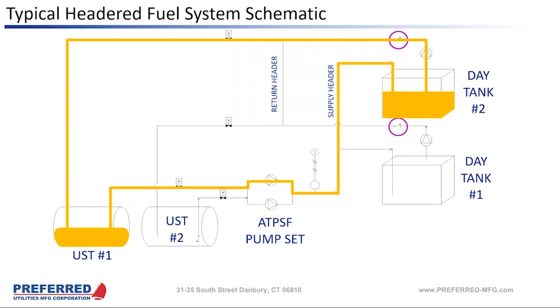So it's one of the reasons that here in the Northeast especially, we really try to push, if at all possible, having a return pump to actively return that fuel back, whether it's a high level condition in that day tank or the fuel is just in bad condition and needs to be returned to the main tank for polishing or removal. That return pump can be even more critical in cold weather situations. Yeah, we're going to see in a slide or two where the return pump is actually part of our strategy for keeping fuel warm.